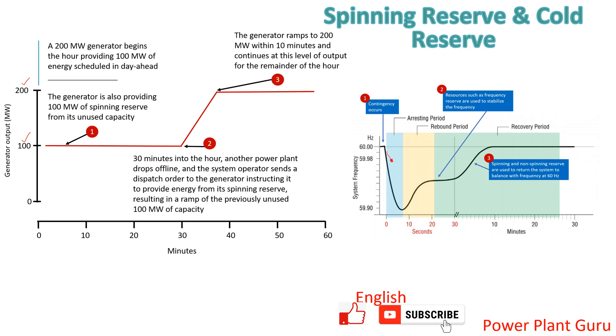The demand is fixed but the supply is reducing. That will cause your frequency to drop — your frequency may go a little bit downwards. Then what the power system owner will tell? Wherever there is a spare capacity, please bring this capacity into the grid. Please pump extra power to maintain whatever power we have lost. So, considering this case of the 200 megawatt capacity machine, the requirement will come to this machine and it will be asked to increase the megawatt. That megawatt will support the power system to increase the frequency. This is how the reserves are used in maintaining the stability of the power system.